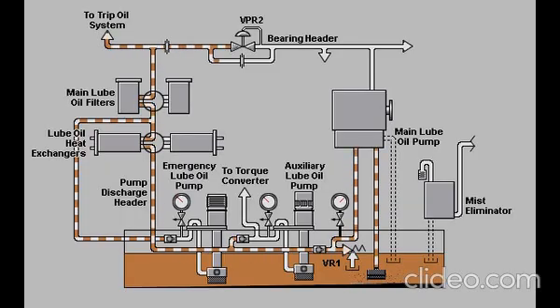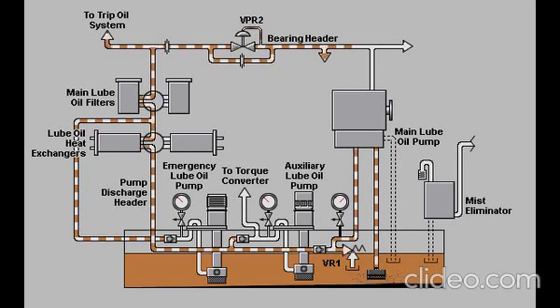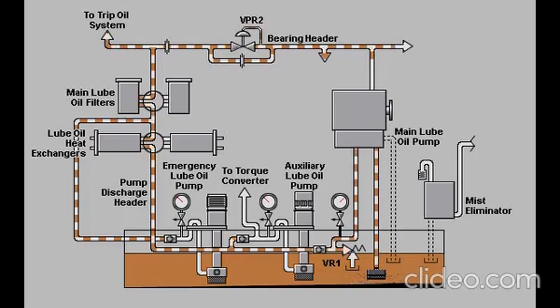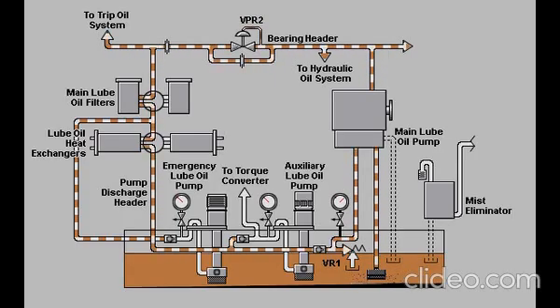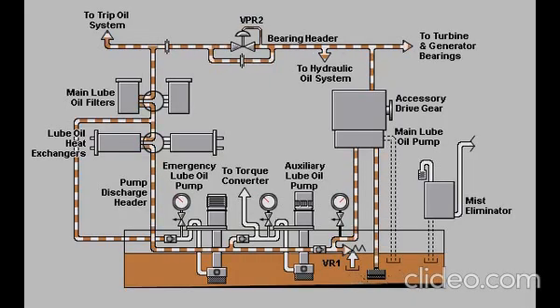VPR2 maintains oil pressure in the bearing header at approximately 26 PSI. The bearing header then supplies filtered lube oil to the hydraulic oil system, accessory drive gear, and the turbine and generator bearings.